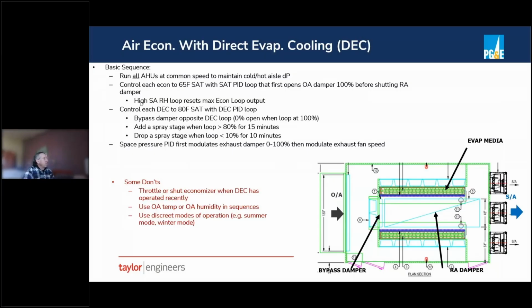We'll have a high supply air relative humidity loop that may reset the economizer maximum. And so what that will do is, if 65-degree supply air is going to result in supply air more than 80% relative humidity, the economizer will say, you can't open the outside air 100%, or you can't shut the return air 100%, because you're going to be too humid at 65. And so it'll basically naturally drift up. It may supply 67, 68, and that naturally brings down the humidity.